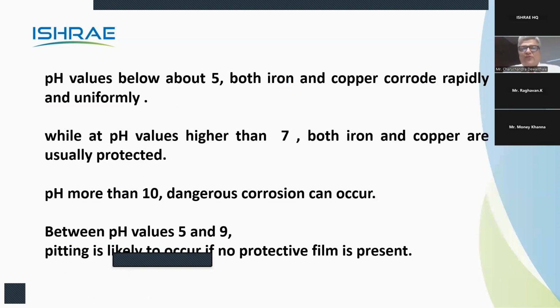Now, when pH value goes below 5, both iron and copper will rust rapidly - corrosion will take place when the pH is below 5. When the pH values are higher than 7, both iron and copper are usually protected. So summing these together: between pH 5 to 9, pitting is likely to occur if the protective film is not formed. One of the things done by the chemistry is to form a protective film over the surface. If pH is more than 10, it becomes dangerous - corrosion can take place, embrittlement can take place.